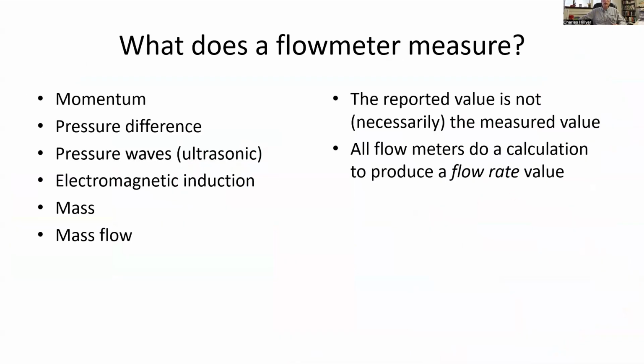Now, it's interesting that a flow meter doesn't usually measure flow. It measures something else that's very closely related to flow. And what it measures gets converted through calculation into a flow rate. But the way it measures those things determines how well the meter works in various circumstances. Now, there are other details about how, for example, if you're measuring momentum, that gets converted into flow rate and how it gets reported to you. But all of these meters involve doing some sort of calculation to produce a flow rate. And the flow rate is generally what you're interested in. Also, the way that these flows are measured affects the accuracy and the durability and the veracity of the flow meter data that you get.